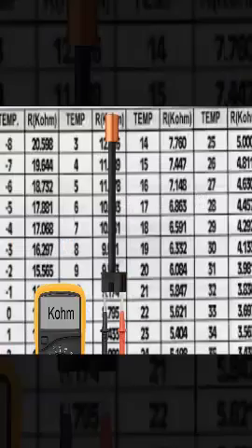4. The multimeter reading should never be 0 or infinite. If the multimeter reads 0 ohms, it indicates that the outdoor temperature sensor is short-circuited. 5. If the multimeter reads infinite, it indicates an open or broken sensor. 6. A proper reading should be around 10 kilo-ohms at 25 degrees Celsius, depending on the sensor.